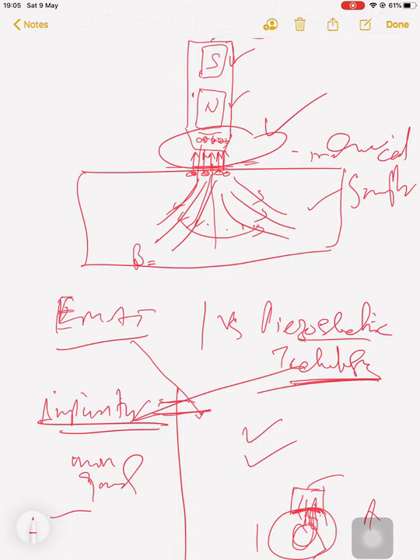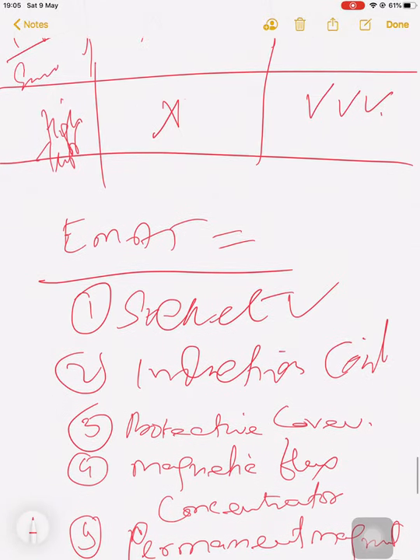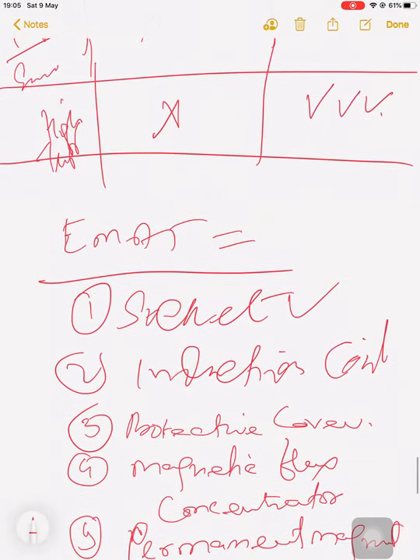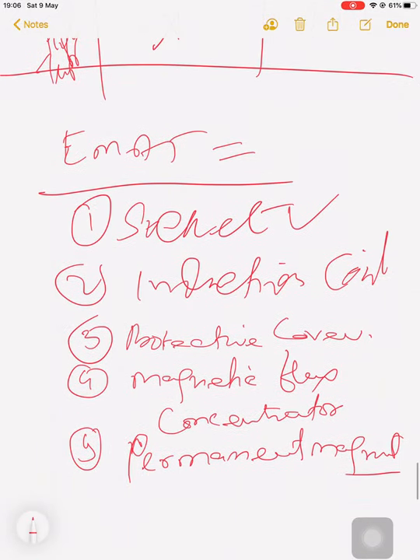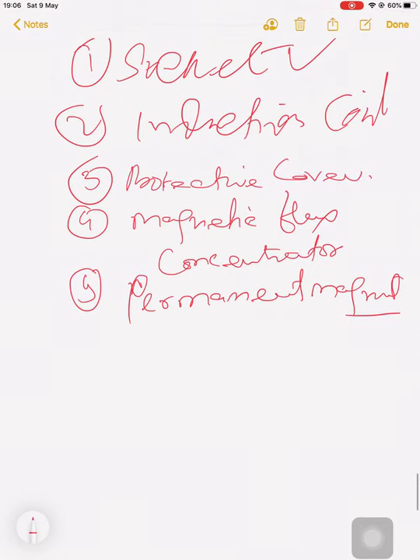These waves propagate in the test objects reflecting and deflecting from the wall back to EMAT coil. The picture created by the ultrasonic activity show flaws and defect within the test object. So EMAT is the only device that is able to transmit and receive transversal shear wave in this way. Wave transmitted by EMAT allow much higher resolutions, higher resolutions and sensitivity to flaws than longitudinal wave produced by the piezoelectric probes.